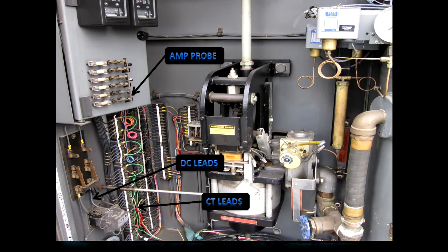And what this test does, and the reason we're monitoring the current, is because this is going to record the current going through the coil on a time basis, and that coil will be energized. It'll release a latch that operates the breaker, and then once the breaker is fully open, it mechanically cuts the power off to the coil. So by seeing when that power is cut off from the coil, we can tell in milliseconds how long it took the breaker to actually operate. All these should open within 4 to 5 milliseconds.